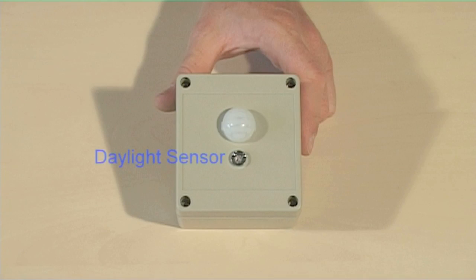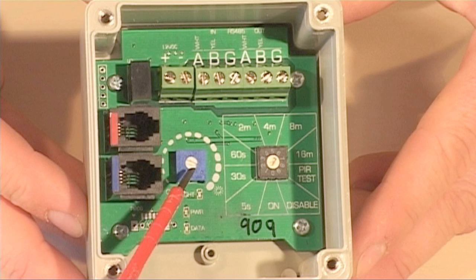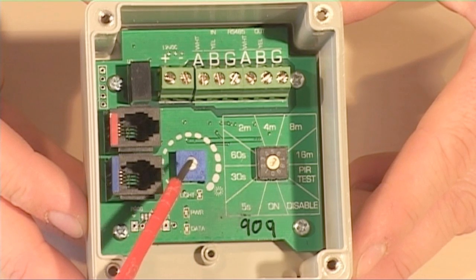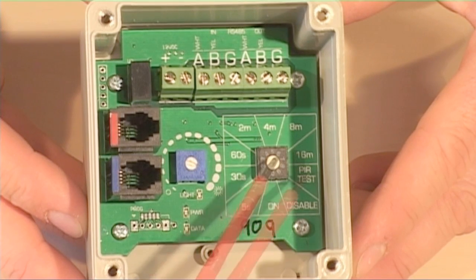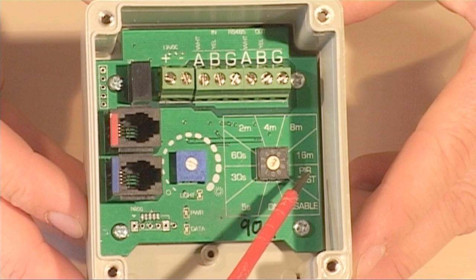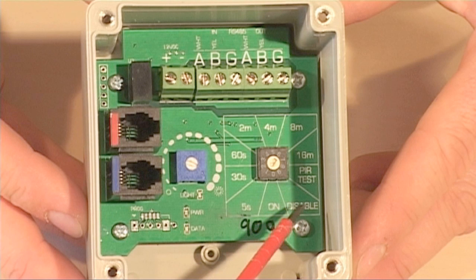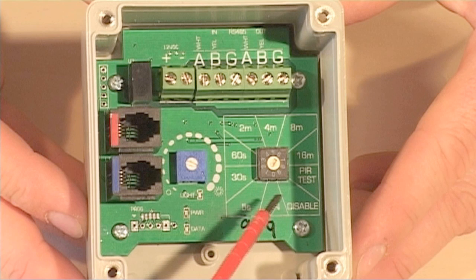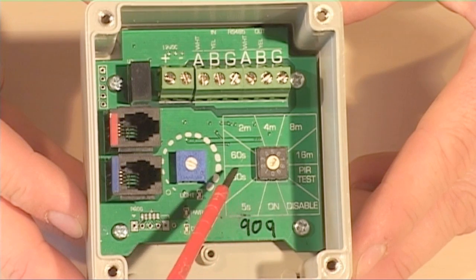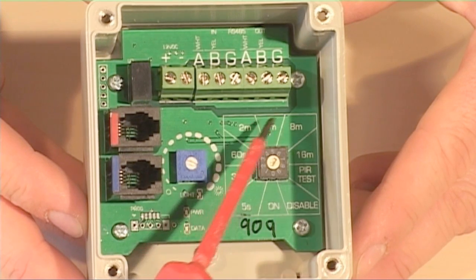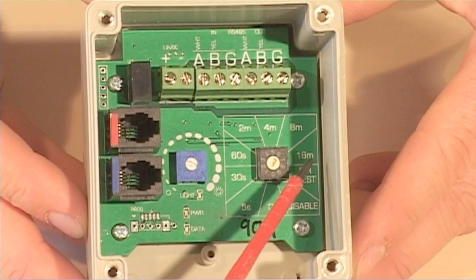Full instructions are supplied with the PIR, which is equipped with the daylight sensor and passive infrared detector, and on the inside there are 2 adjusters. One is to set the threshold between daylight and night. The other allows the PIR to be tested and set up, disabled, set to permanently on, or to determine the length of time that the lights remain on after activation.